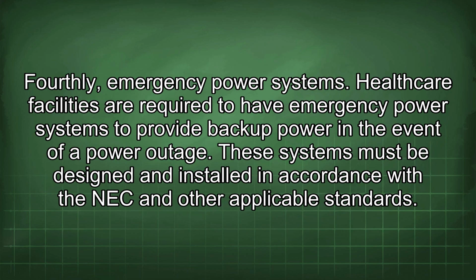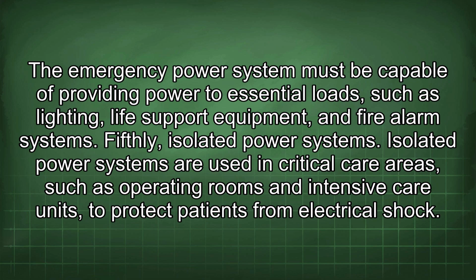Fourthly, emergency power systems. Healthcare facilities are required to have emergency power systems to provide backup power in the event of a power outage. These systems must be designed and installed in accordance with the NEC and other applicable standards. The emergency power system must be capable of providing power to essential loads, such as lighting, life support equipment, and fire alarm systems. Fifthly, isolated power systems.